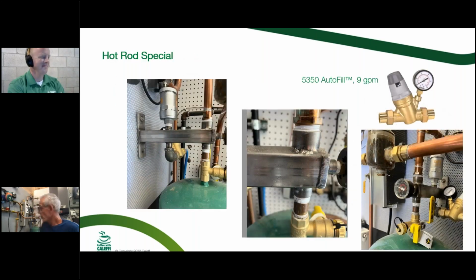And so, just to brag a little bit, right behind me, if you can see in the picture, is one I made. I thought, what if I made one out of stainless steel? I just built that, and I made it 3/4 and 1/2, so it could be used for domestic water or hydronic water. Just flip it over, and now you've got a 3/4 connection. But you can see I put an air vent on there. I hooked it to my system. I got my fill valve off to one side of it. So it's, again, just an example of a multi-function mounting bracket for an expansion tank, and fill. You could put a relief valve up there too if you wanted.